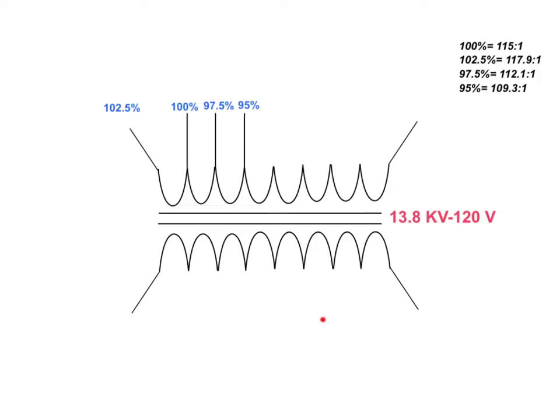If you want to increase your secondary voltage because of the voltage terminal drop, because you've loaded your transformer, you go down on your taps. You do not go up. Which is why, again, we use these ratings here.